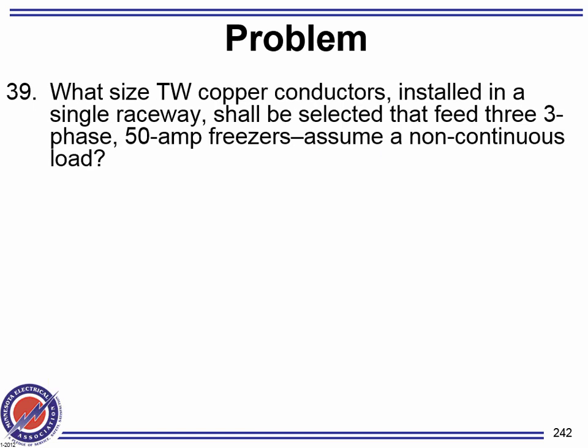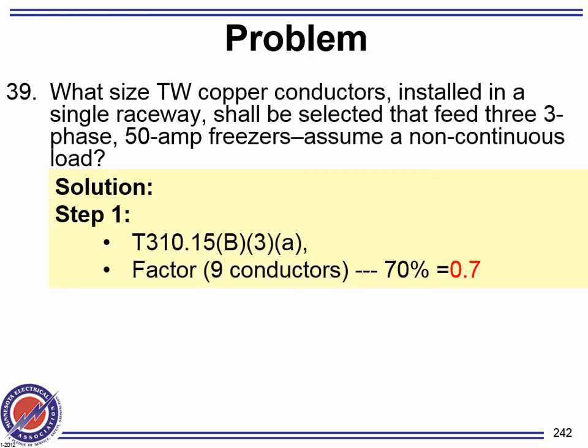What size THW copper conductor installed in a single raceway shall be selected to feed a three-phase 50 amp freezer, assuming non-continuous? If it was continuous, what would you do? You size based on 1.25, put it aside. Then you go size based on the rating and find the answer. And what do you do? Pick the largest of the two. Okay, so in this case, it's not continuous.